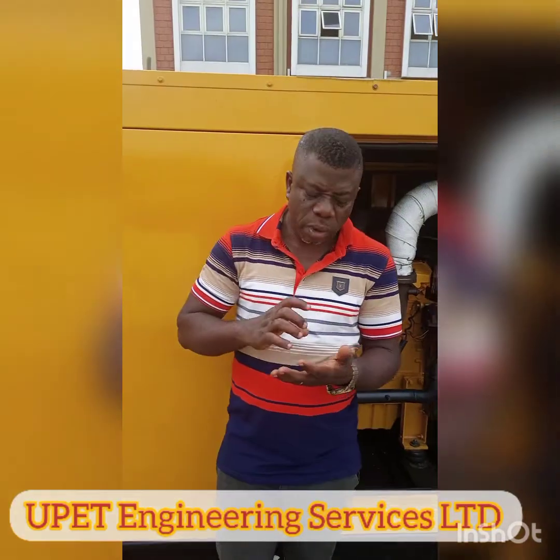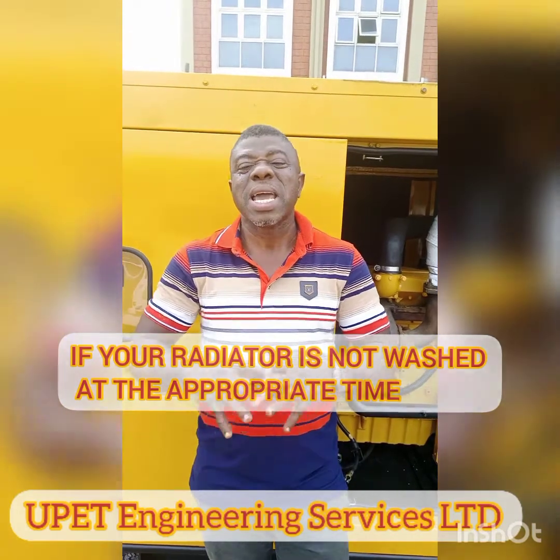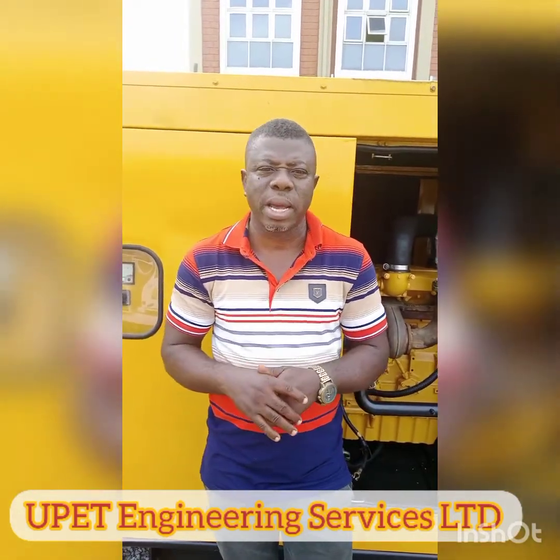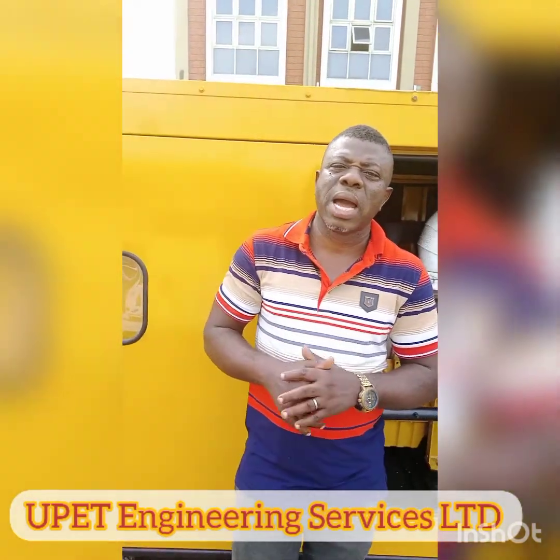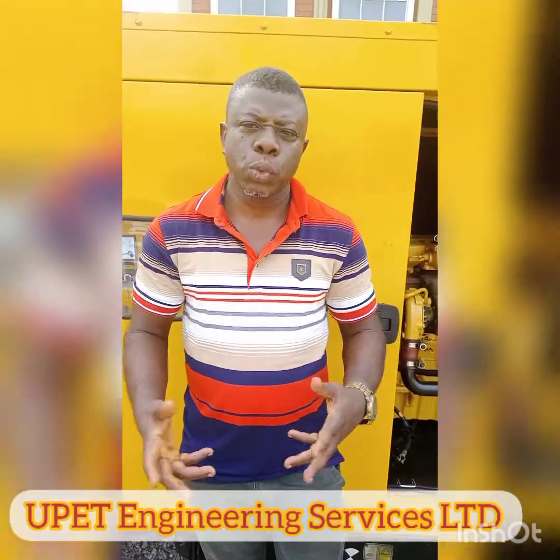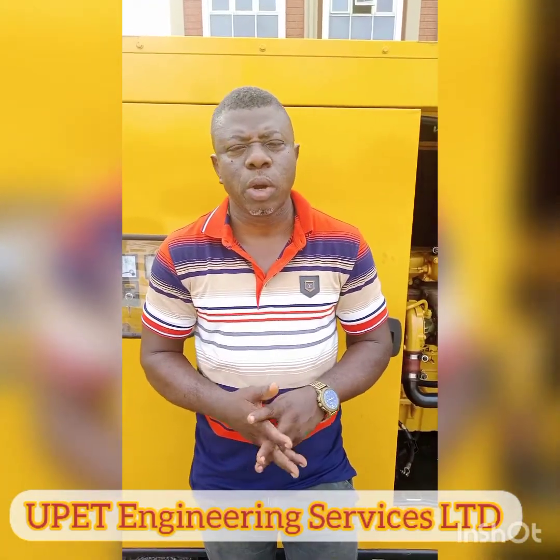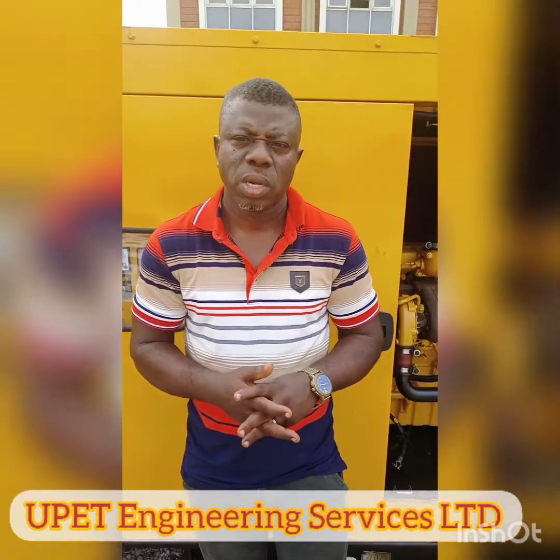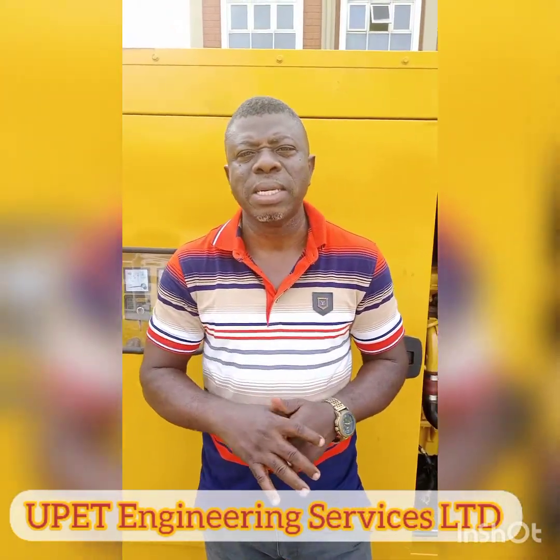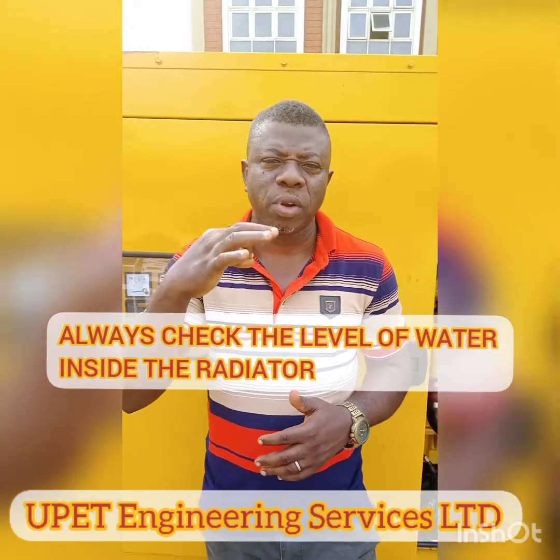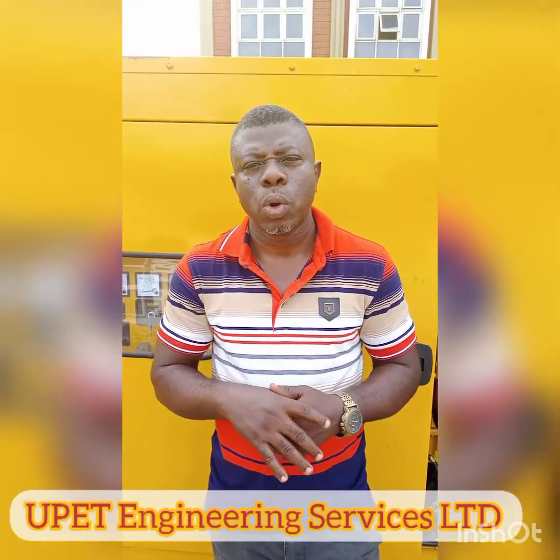Number one, if your radiator is not washed at the appropriate time, the radiator is supposed to be flushed. That is if the area is not a market area, because a market area is prone to dust and so many things. But in a normal environment, it is expected that you wash your radiator within 600 to 750 hours. Number two, before you even start checking the condition of the radiator, whether it's choked or not, you have to check the level of the water inside your radiator, because once the level of that water goes down, the temperature will be rising.